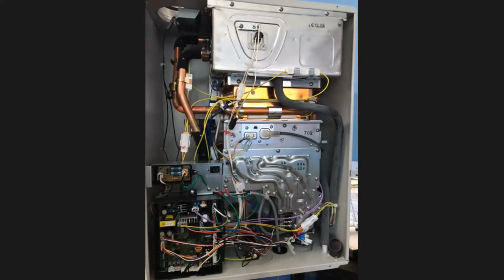So John, I see you're asking there about a water softener. Interestingly, we actually have some pretty soft water here in New England in a lot of cases, and that actually attacks within the piping. So we try to stay away from creating overly soft water. And then water softeners tend to be salt, so again, it's another consideration as we're doing that. But generally, New England doesn't have hard water that requires softening, even though we tend to see it a lot. I'm working with a project right now, and they've had issues because their water's too soft, and the water treatment company came in and offered a water softener as an answer. So hey, kind of going the wrong direction.